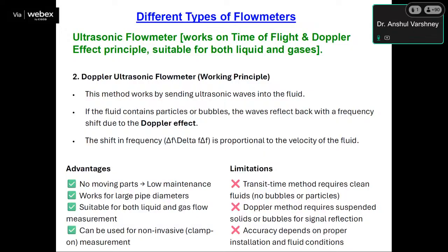The limitation of the transit time method is that it requires a clean fluid. There should be no bubbles or particles. The Doppler method requires suspended solids or bubbles for signal reflection. Accuracy depends on proper installation and fluid conditions. The accuracy of ultrasonic flow meters is not as good as electromagnetic flow meters, mass flow meters, or any other type of flow meters.